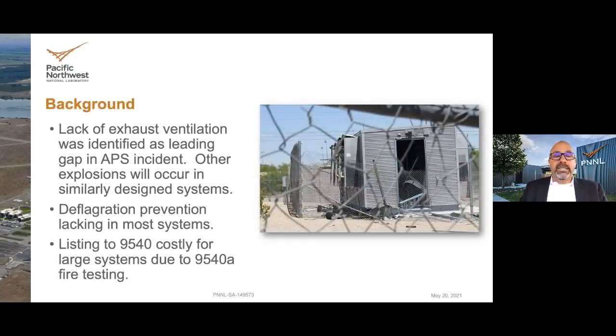We've already mentioned a couple of these incidents, that the lack of exhaust ventilation was the leading gap in the Arizona incident, and other explosions will occur in similar design systems. There are many installed. Deflagration prevention is a term in the NFPA 855 code as one of the ways of addressing explosion control. Either you can have blowout vents, or deflagration prevention means an exhaust system, an air dilution system, to get rid of the flammable gases. A listing to UL 9540 is a very costly endeavor for a large one-off system, because you have to do fire testing and you're not going to destroy the one device you're installing. So the industry is moving towards a more modularized approach.